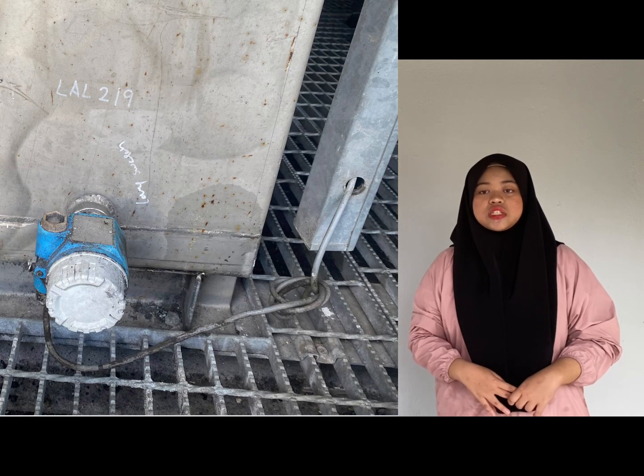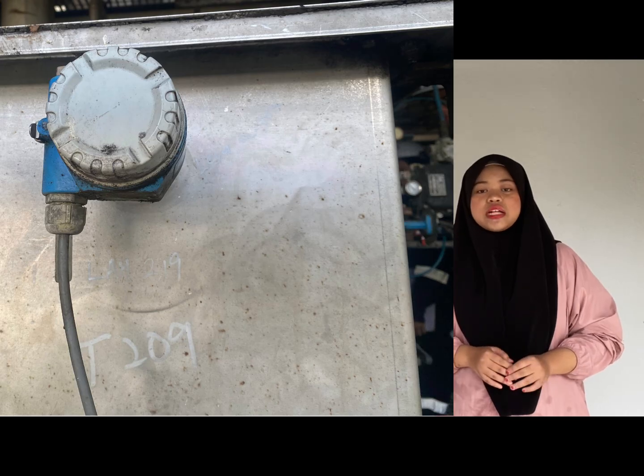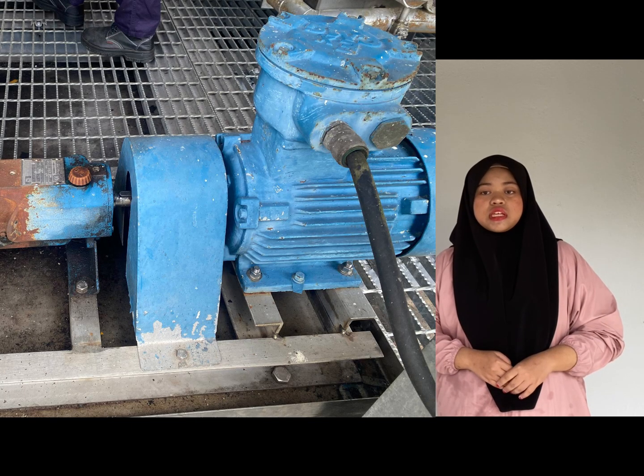Once the physical and electrical parts are verified intact, the execution flow strictly commands the sequential power-up phase, where timing and sequence are vital to prevent electrical surge or system fault. The sequence initiates at the hardware source by switching on the molded case circuit breaker (MCCB) to energize the main power rail. Immediately following grid stabilization, the flow transitions to the automation layer by switching on the PLC system module, initializing the central processing unit and activating the optical isolation modules. With the PLC logic engine online, the process culminates in switching on the SCADA control system. This boots the central graphical user interface, instantly establishing real-time communication links and initializing live data feeds for the LAH219 high alarm and LAL219 low alarm level matrices.